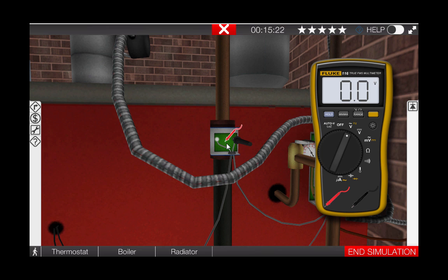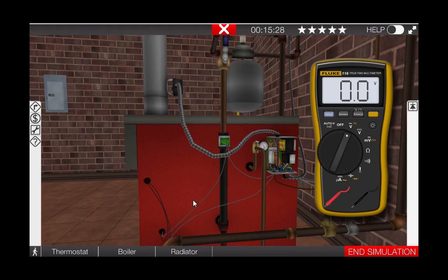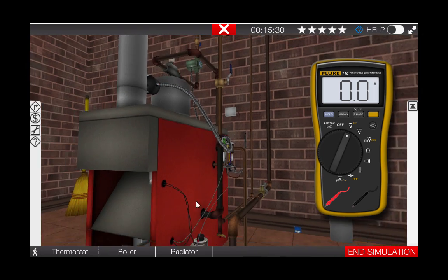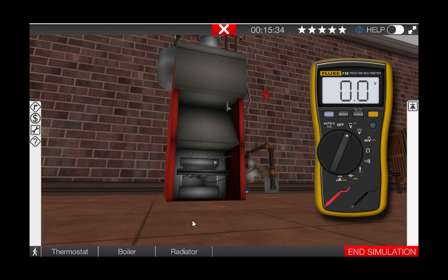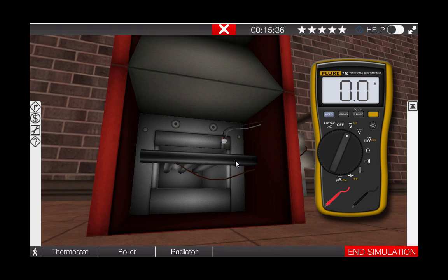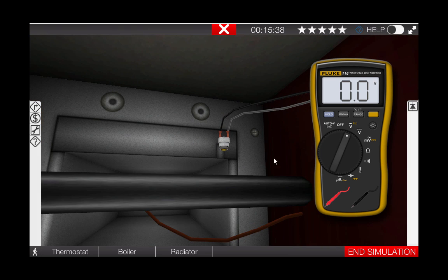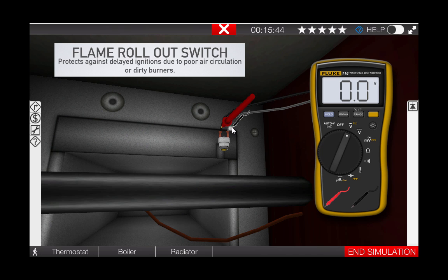Next, we'll store the meter leads temporarily back at the multimeter and go to the flame rollout switch. The rollout switch is at the bottom of the boiler, just in front of the burners, and protects against delayed ignitions due to poor air circulation or dirty burners. Click on the leads and place them at the glowing hotspots at the flame rollout switch. Zero volts is measured here, indicating that the flame rollout switch is closed and intact.